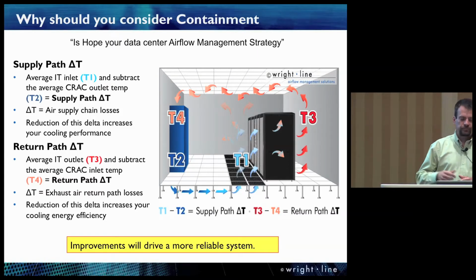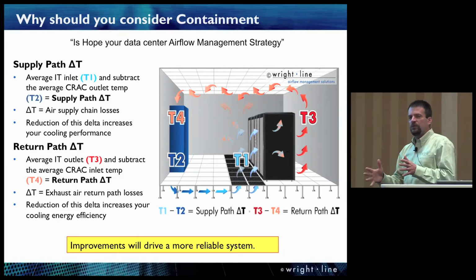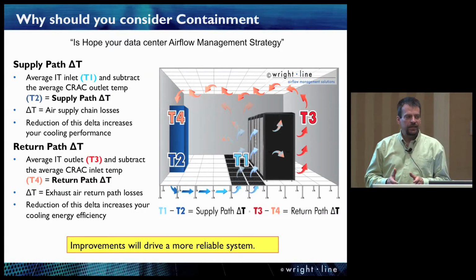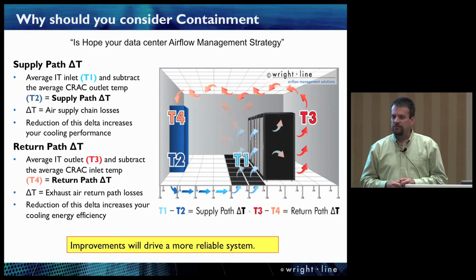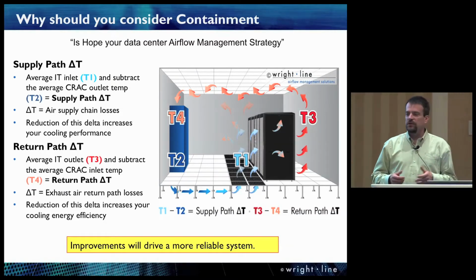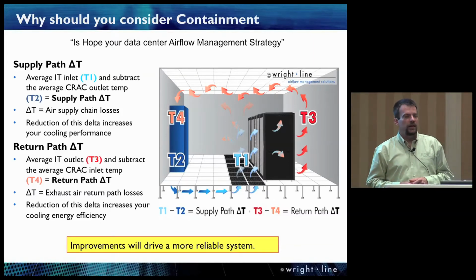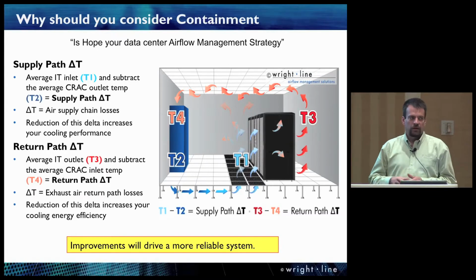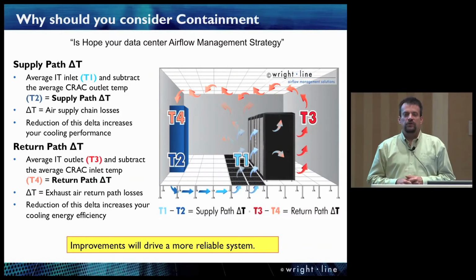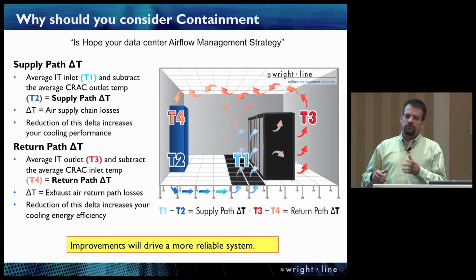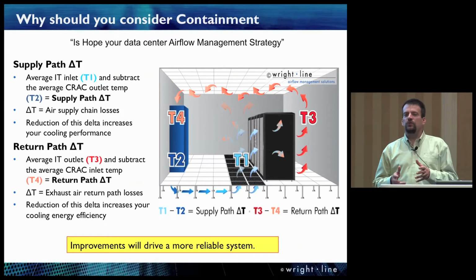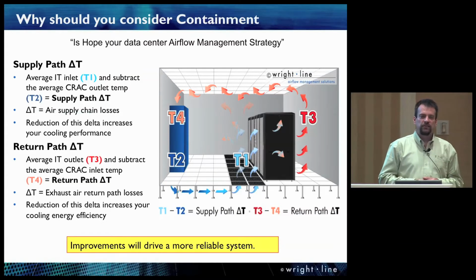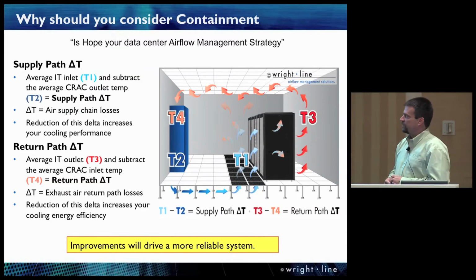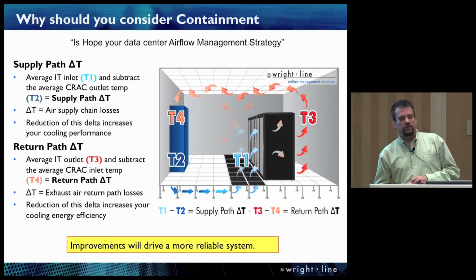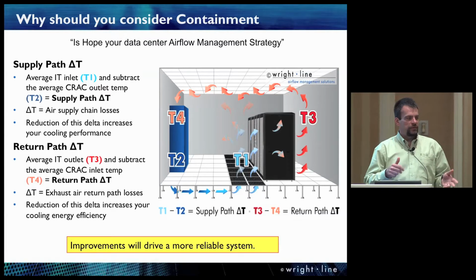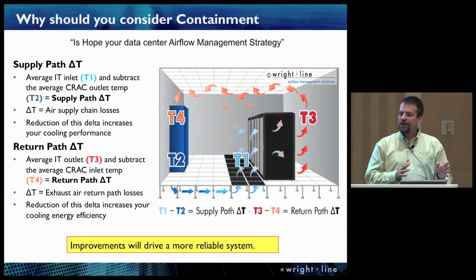Conversely, turn that around. In the return path, if I go right to the outlet of the server equipment or any of the IT equipment in a data center, and I meter that temperature coming out, it's actually quite warm. It would not be unrealistic to see in the 90s in that exit temperature of a piece of IT equipment. However, when I look at the return temperature of the HVAC equipment, it's nowhere near 90 degrees. Historically, I see that somewhere in the high 70s, if I'm lucky, in a legacy type data center. So ideally, what we're trying to do is identify the supply path delta T and the return path delta T, and drive solutions in each one of them.